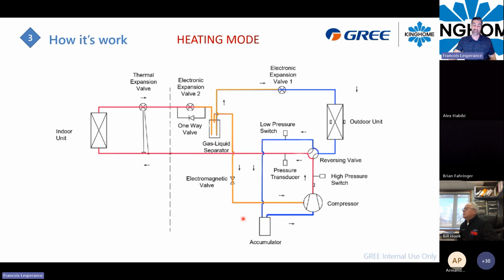So the little difference between those two cycles is that the reversing valve in heating is active, so the refrigerant will flow in a different direction. And also in very cold temperature, we will have this vapor injection process active when it's very cold outside.